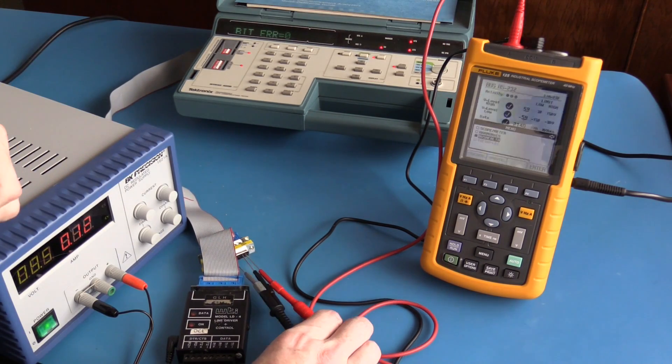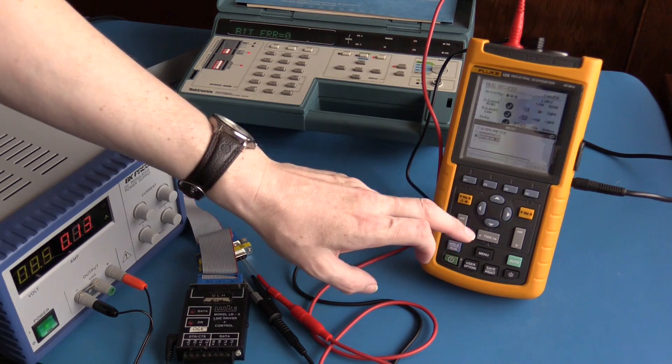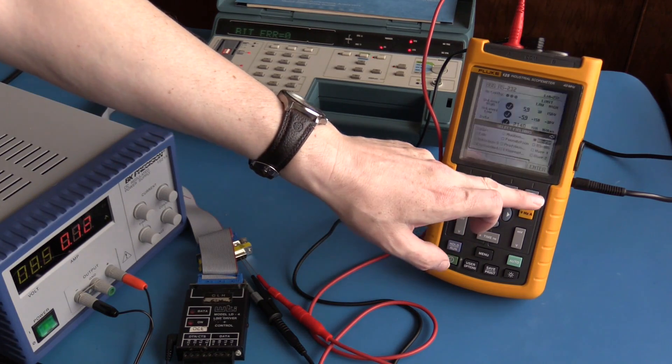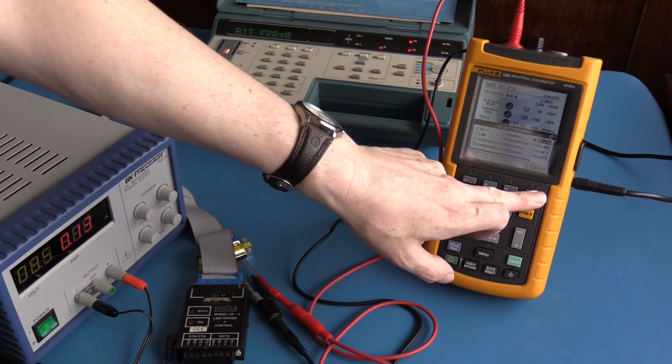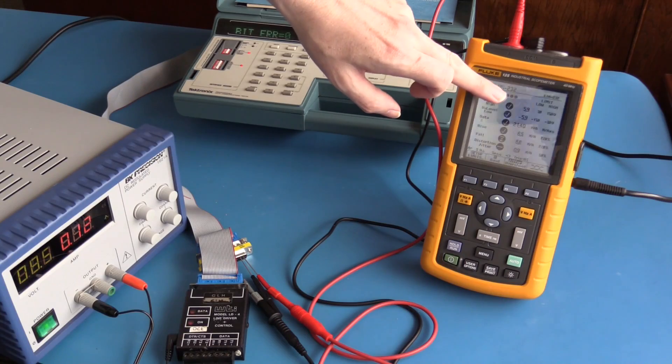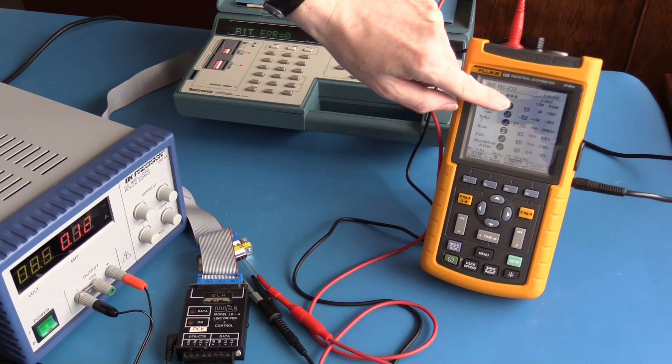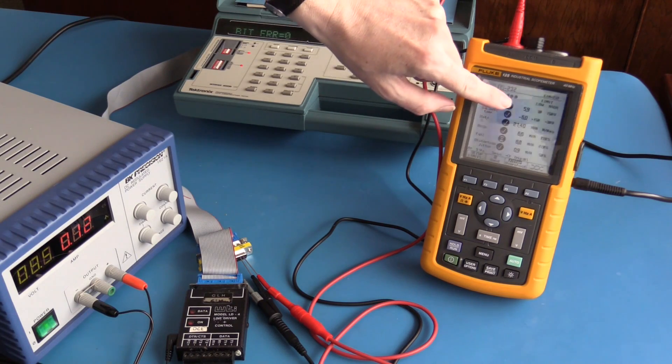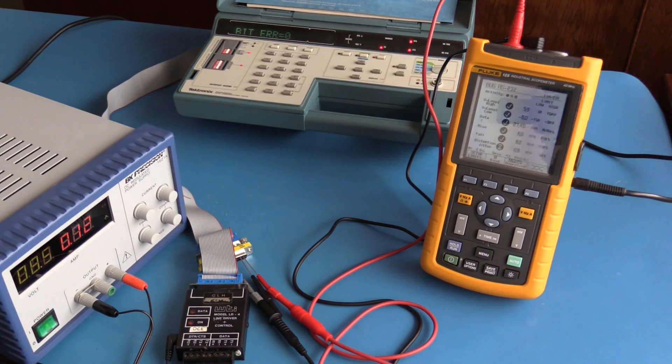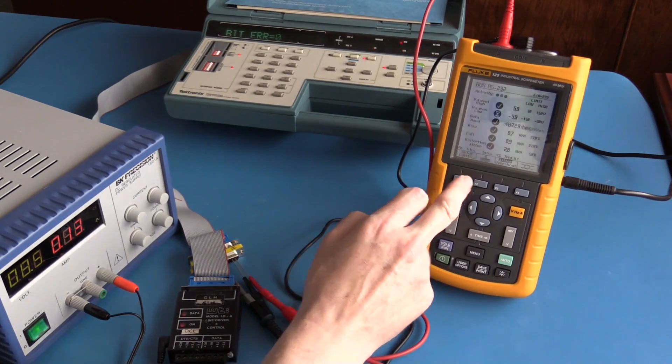Select bus health and RS-232. From these three dots we can see that we have a signal and we have data. The bus health check is telling us that all of the expected signal parameters are okay. I can select baud to see the number of bits per second.